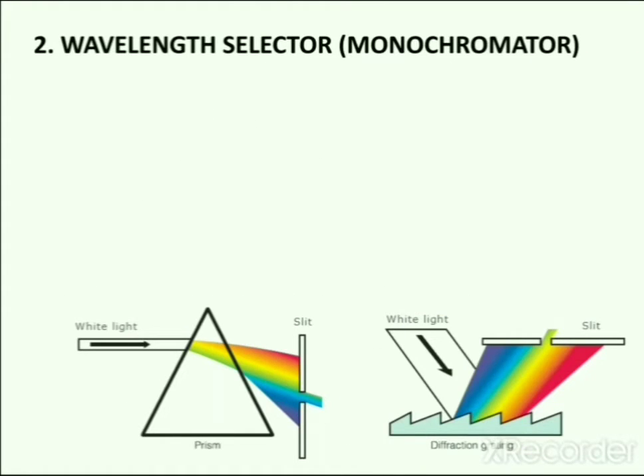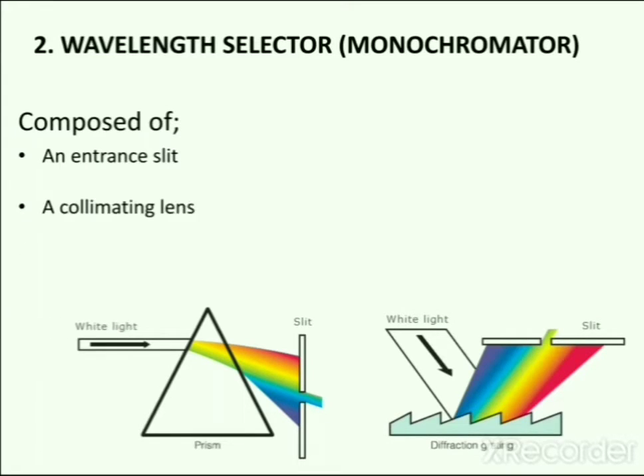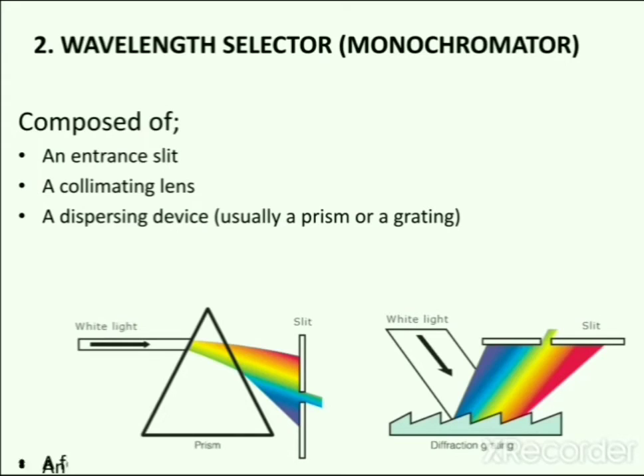The next part of the IR instrument is the wavelength selector — the monochromator. A monochromator is an optical device that transmits a mechanically selected narrow band of wavelengths of light chosen from a wider range of wavelengths available at the input. It is composed of an entrance slit, a collimating lens, a dispersing device (usually a prism or grating), a focusing lens, and an exit slit. Light radiation passes through the entrance slit and is incident upon the dispersing device, which converts the light into its constituent wavelengths. The exit slit allows only a single wavelength to pass at one time, thus converting polychromatic light into monochromatic light.